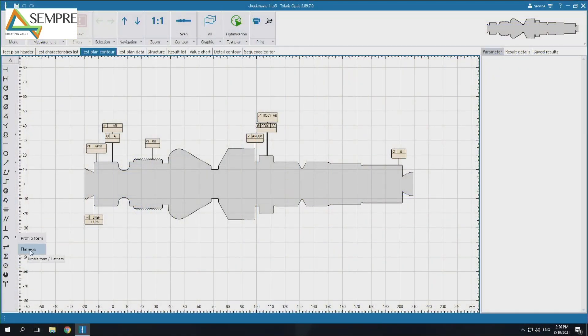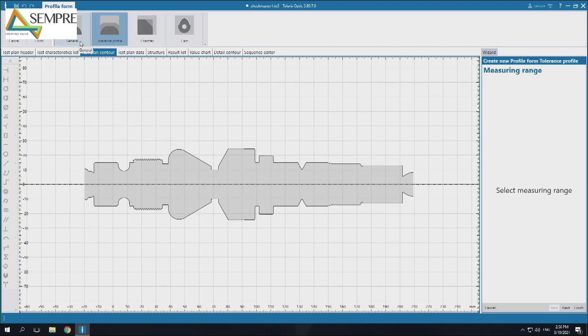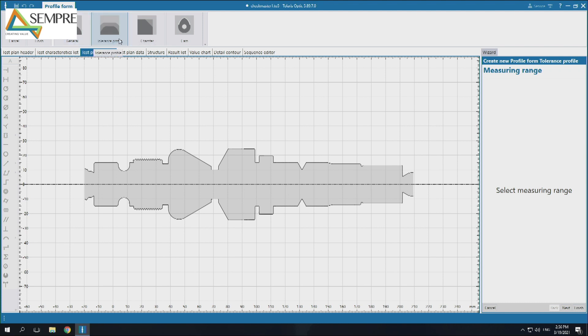You can see that flatness is an option, and it's only an option because we're on T3D which also does flatness. Usually that isn't available. Under profile form we've got some options of different profile forms. We're going to be looking at two in this case: general and the tolerance profile. I'll start with the tolerance profile.